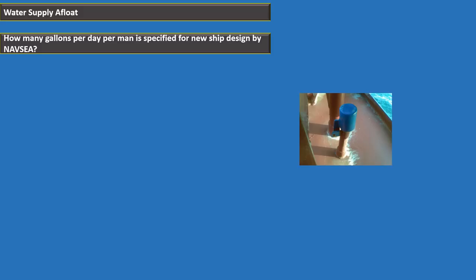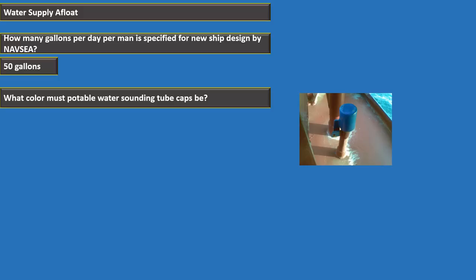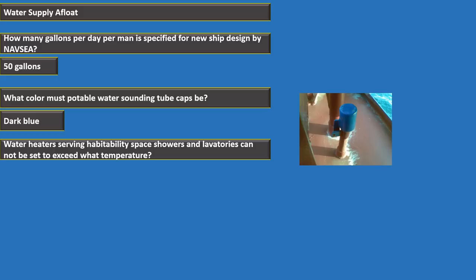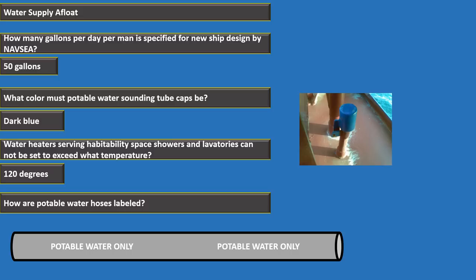Water supply afloat: NAVSEA specifies 50 gallons per day per man for new ship designs. Potable water sounding tube caps must be dark blue. Water heaters serving habitability spaces, showers, and lavatories cannot exceed 120 degrees. Potable water hoses are labeled 'POTABLE WATER ONLY' in one-inch white letters every 10 feet.